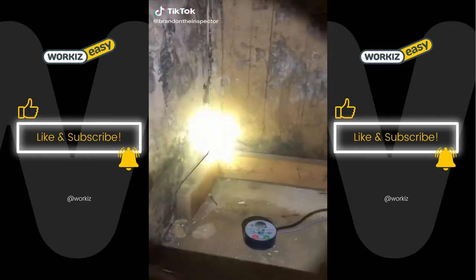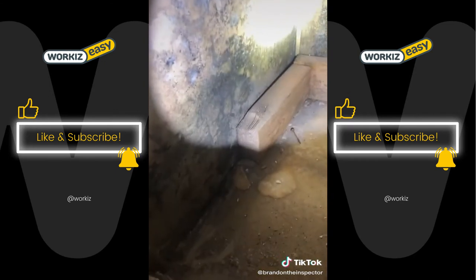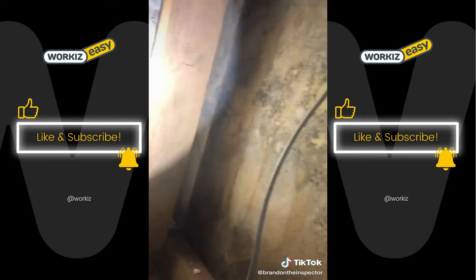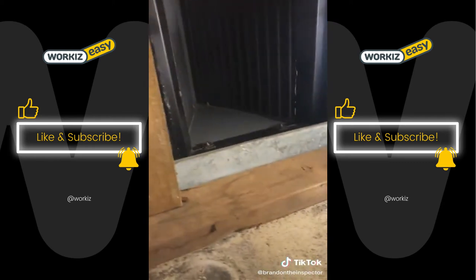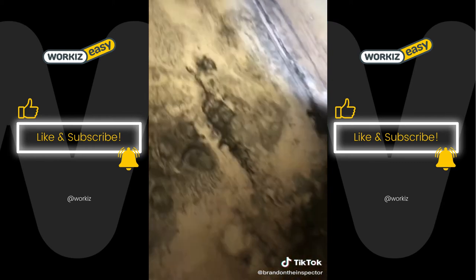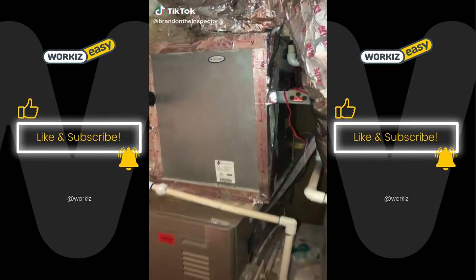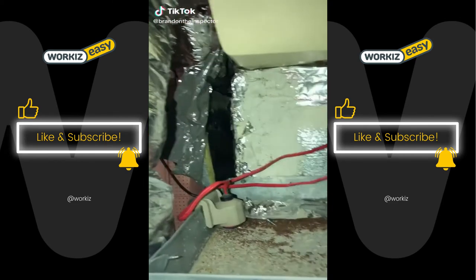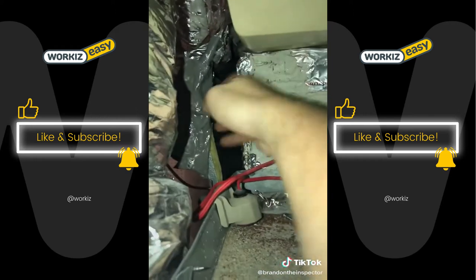Opened up the return vent. Dumbasses used drywall and wood for return ductwork, and lo and behold, mold. Science experiment. More mold. Oh look, there's the inside of the unit. Dumbasses. So we have just a little bit of cold air escaping. Just a little gap. Tiny, tiny little gap.